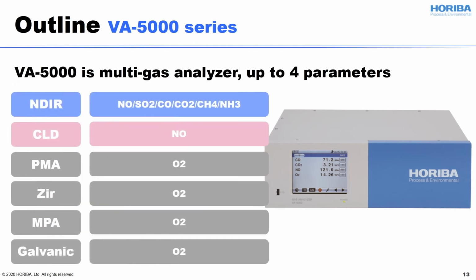So, the VA-5000 can make multiple measurements of up to 4 parameters. You can measure NO, SO2, CO, CO2, CH4, ammonia, and moreover N2O, propane, etc. Those parameters are measured by NDIR. Also, another chemiluminescence module can make NO measurement, especially at low concentration. All CEMS users need this chemiluminescence for the NO measurement. For O2 measurements, there are 4 selections of O2 measurement principle: PMA, Zirconium, MPA, and Galvanic. I am going to explain in detail later.